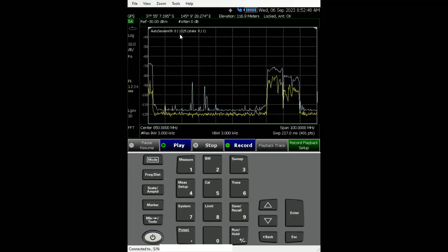So to clarify that, if the session data says you have 1225 traces left, a record limit, that's the trace limit that you're going to hit when you start the recording. So anyway, done with this, I can show you again if I try to do a recording because it has run out of memory right now, and you should see the error popping out again. So it says cannot record at trace record limit. Okay.